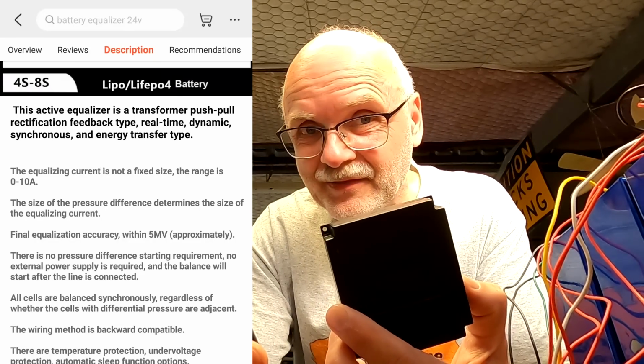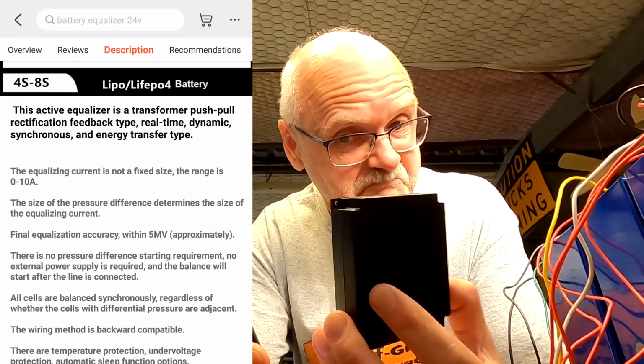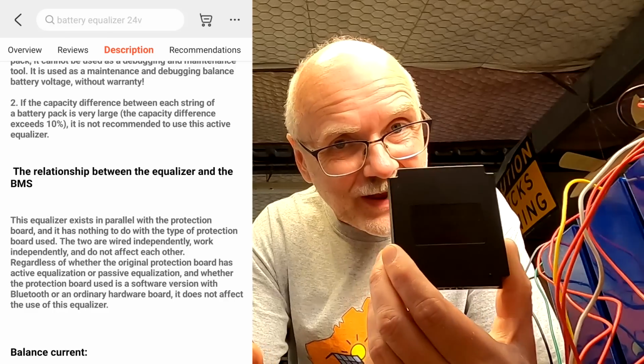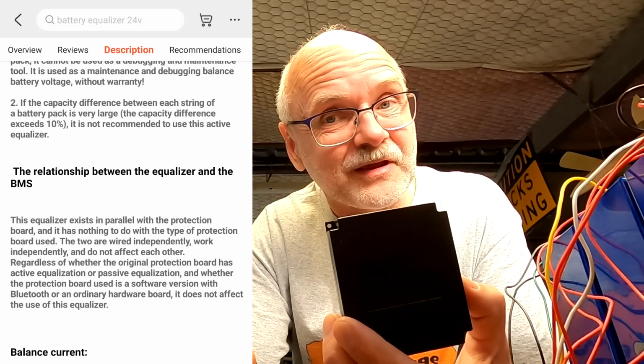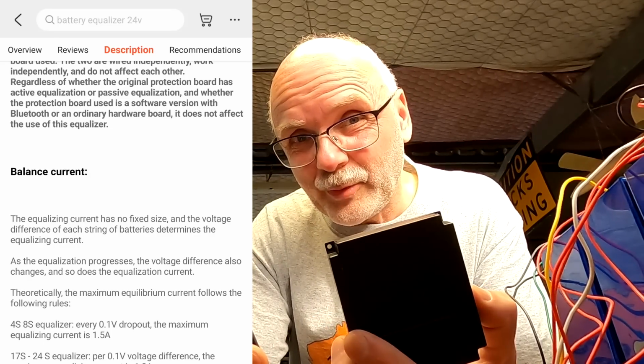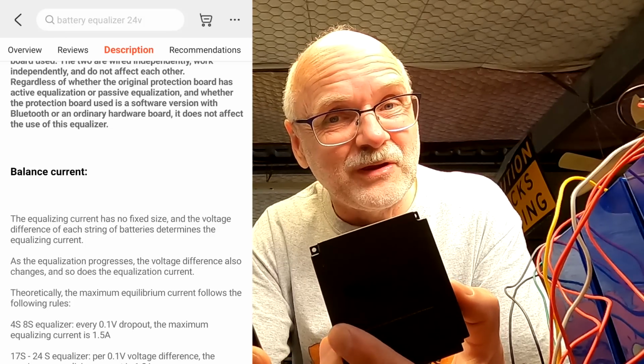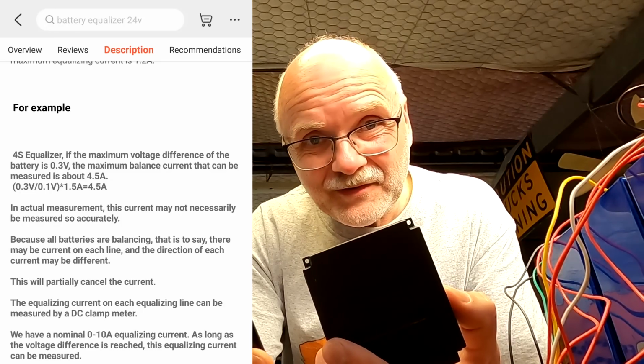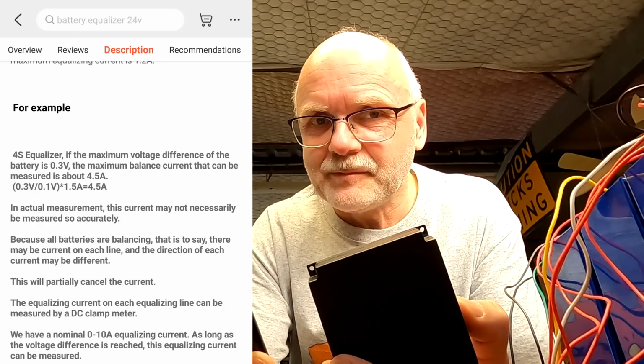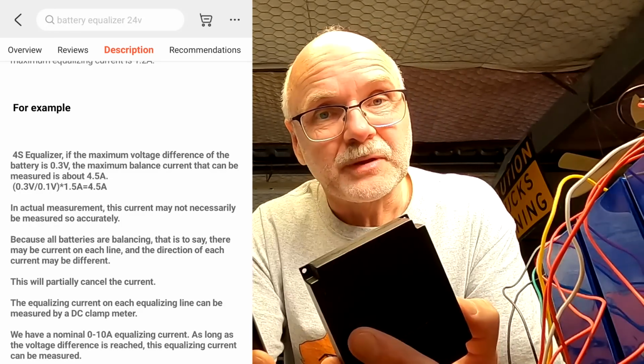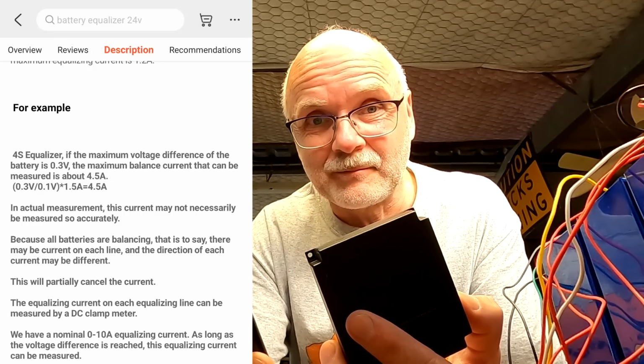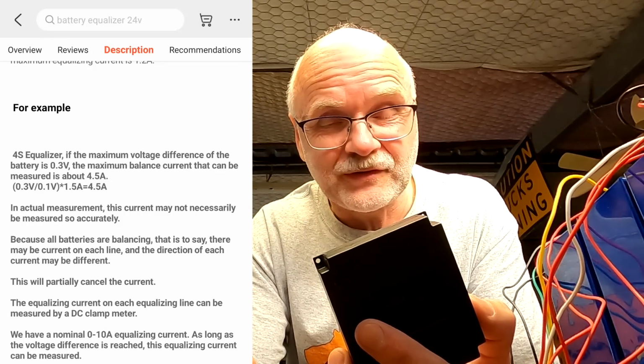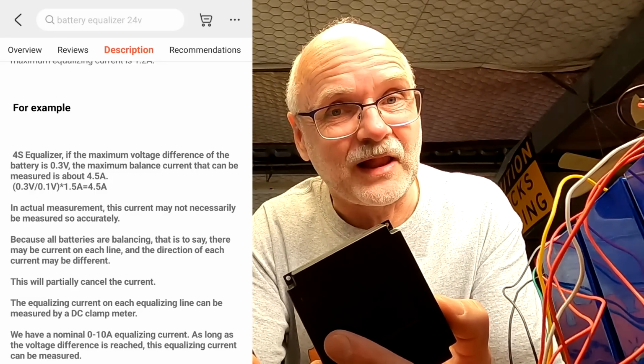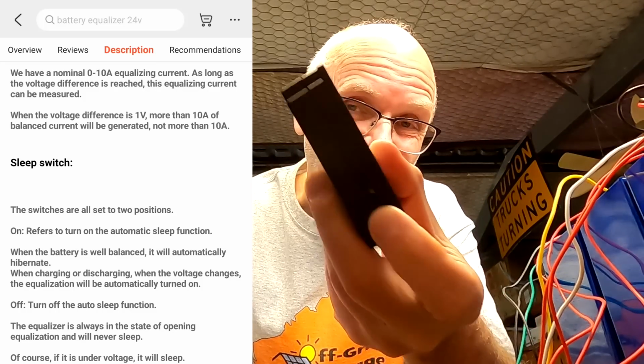This is the HELTEC 10 amp active balancer, $40.28 Australian. The balance current can be in the range of 0 to 10 amps. The active balancer can be connected to any BMS in parallel. A balance current of 1.5 amps can be reached for every 100 millivolt deviation. The balance current on each balance cable can be measured with a DC clamp meter. Because all batteries are balanced at the same time, balance current can flow in both directions and therefore cancel itself out when measured. Sleep switch.